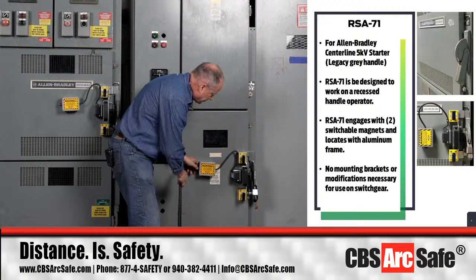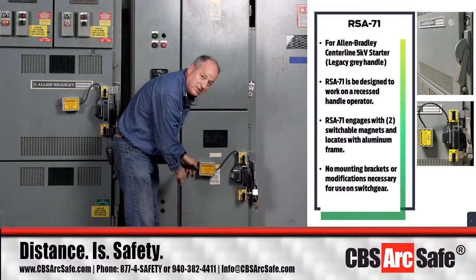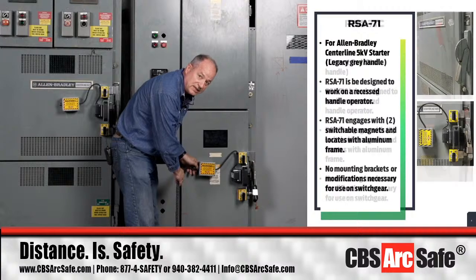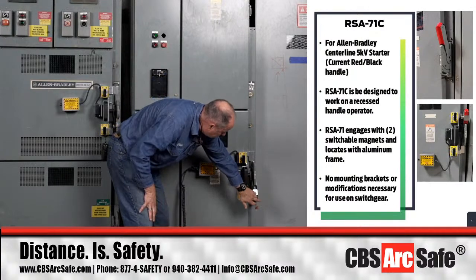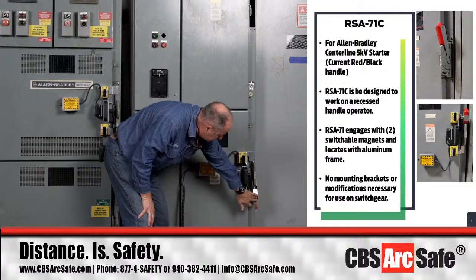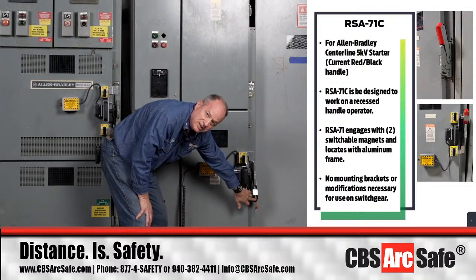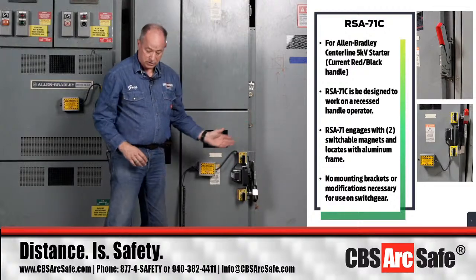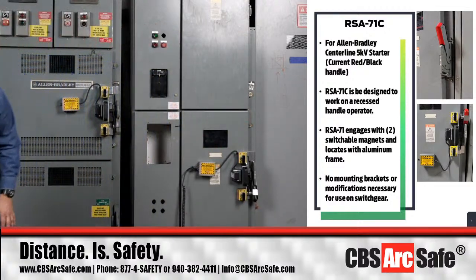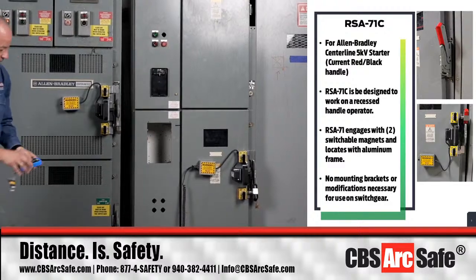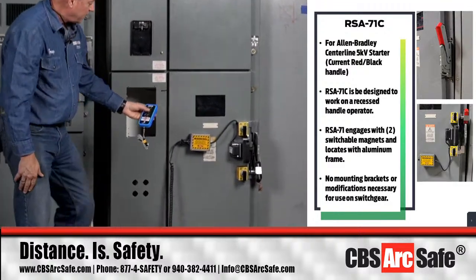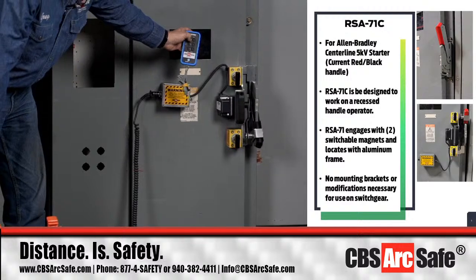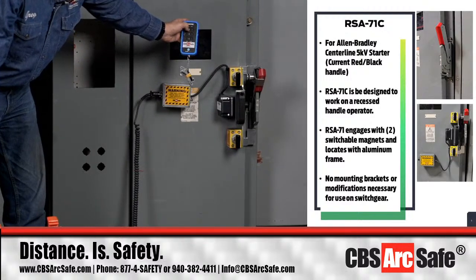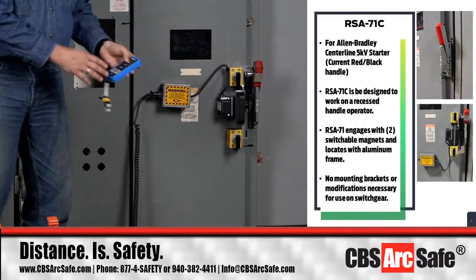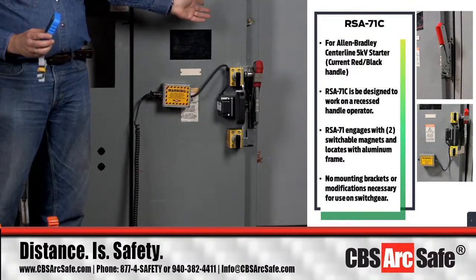The first one we looked at was the original RSA-71. This is the RSA-71C, and again it operates the black and red handle. You'll see it looks black right now. When it comes to the closed position, you're going to see it go to red, so you'll be able to see when we go from trip to close, the red side of the handle shows up. That's what we mean by a red and black plastic handle.